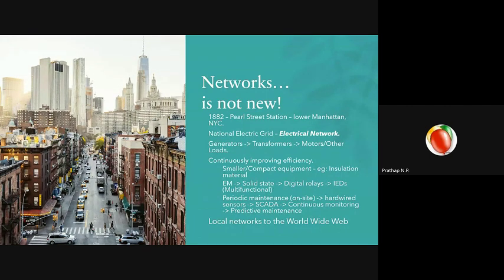So from electromagnetic relay, sorry, electromechanical relays, when it initially started, we transitioned from there to solid state relays. So it brought the size a little bit down. During electromechanical times, every single phase had a separate relay. For example, if you have an overcurrent relay, A phase, B phase, and C phase each will have its own relays, and they'll be huge, tall, and heavy.